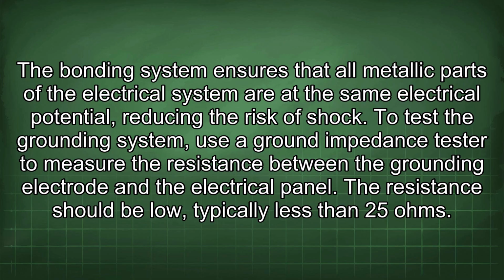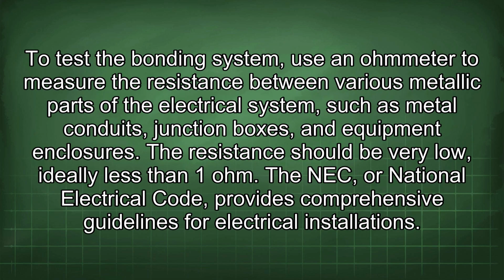The bonding system ensures that all metallic parts of the electrical system are at the same electrical potential, reducing the risk of shock. To test the grounding system, use a ground impedance tester to measure the resistance between the grounding electrode and the electrical panel. The resistance should be low, typically less than 25 ohms. To test the bonding system, use an ohmmeter to measure the resistance between various metallic parts of the electrical system, such as metal conduits, junction boxes, and equipment enclosures. The resistance should be very low, ideally less than 1 ohm.